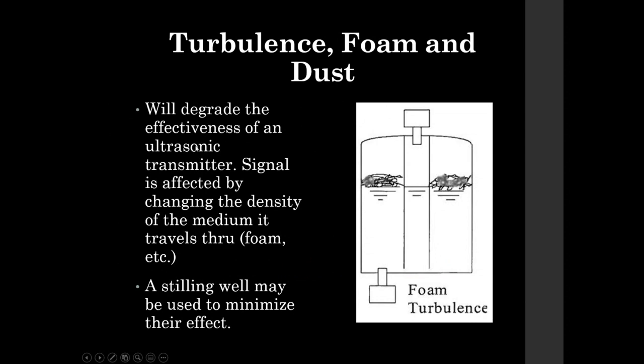They will degrade the effectiveness of the signal because that signal is affected by the density of the medium that it travels through. So in a perfect situation, it's just air between the transmitter and the surface level, but often you'll get different things in there, dust, foam, turbulence, and we'll talk about different considerations that we have to use in order to mitigate some of those problems and still be able to use these devices.